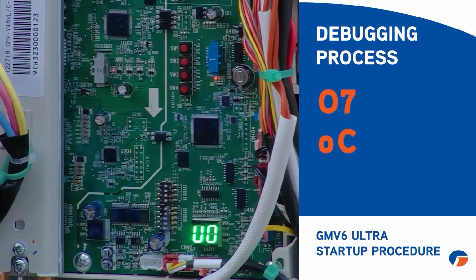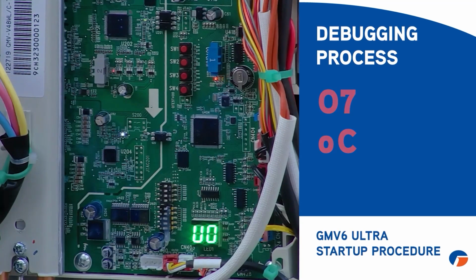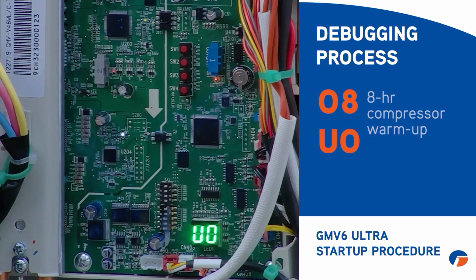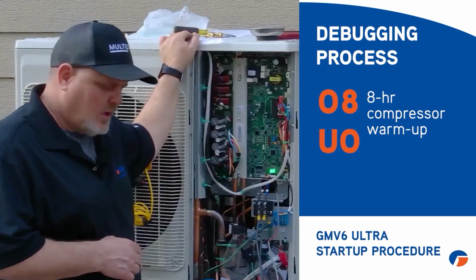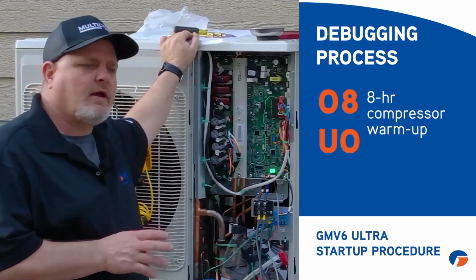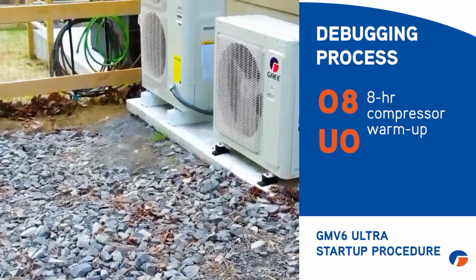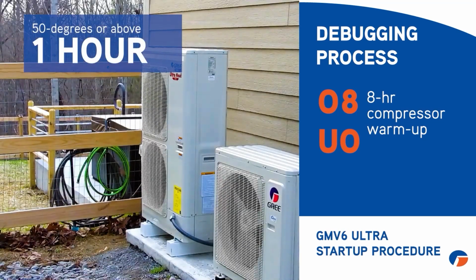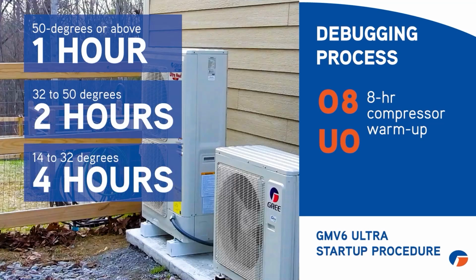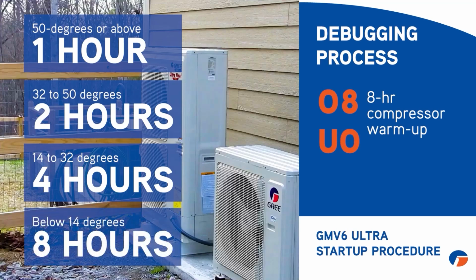If there's something wrong, it'll stop debug and give you an error code. 08UO. What that means is this machine requires an 8-hour compressor warm-up. This has been powered for at least 2 hours or so. We do allow you to override that with rules. If it's 50 degrees or above, it's 1 hour. If it's 32 to 50, it's 2 hours. 14 to 32, it's 4 hours. Below 14 degrees, it's the full 8 hours.